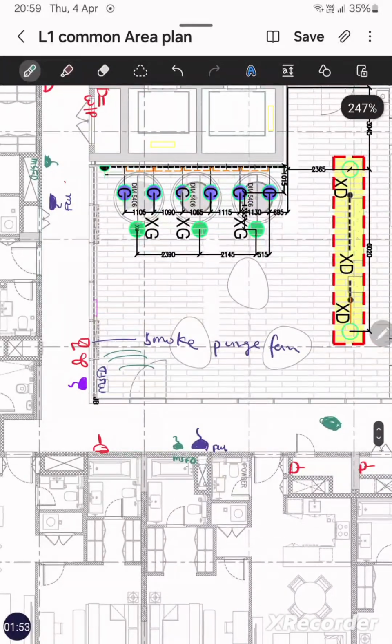But in case of fresh air, all the time this MSFD will be open in normal condition, and it will supply the fresh air to the corridor. But once the fire is detected, the fire will increase more and more when there is fresh air, when there is oxygen. So we have to cut the oxygen in the fire zone area. So the damper should close. So during fire, the damper will close.